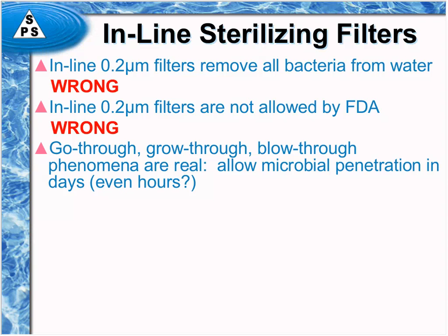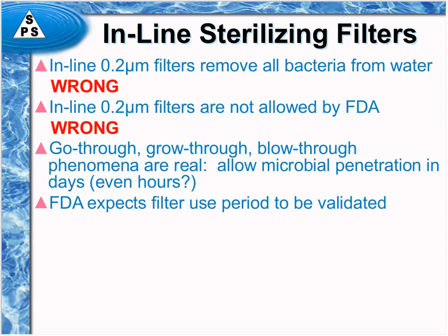Long-term service of the filter is one of the hallmarks of what causes that. FDA does expect filter use to be validated. They want that period to be determined because they know that the longer a filter is in service, the more likely organisms are eventually going to get through that filter.